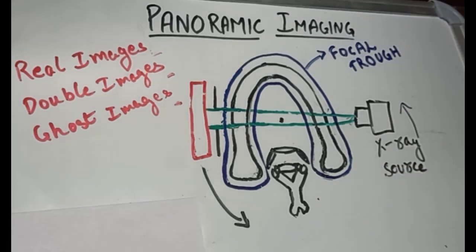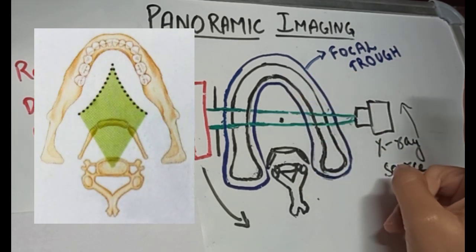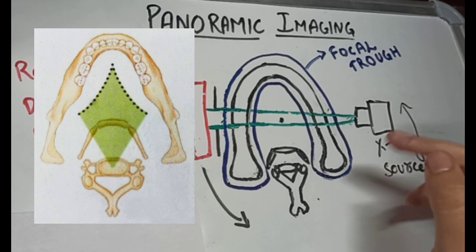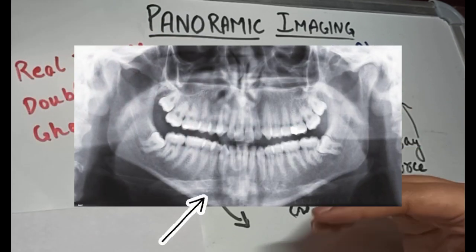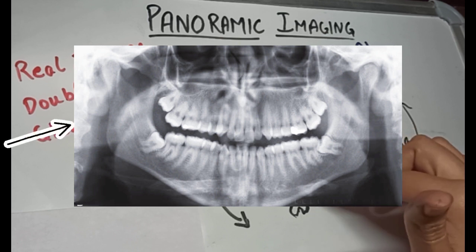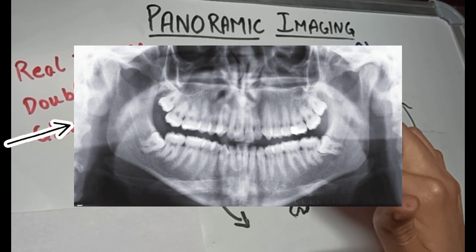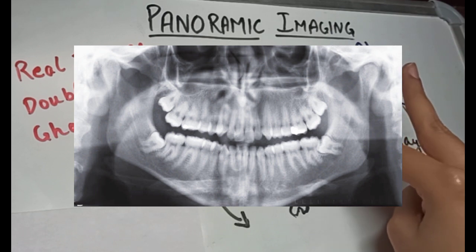Objects that lie posterior to the center of rotation and are intercepted twice by the x-ray beam form double images. For example, the hyoid bone, the epiglottis, and the cervical spine all cast double images because they are intercepted twice by the x-ray beam.